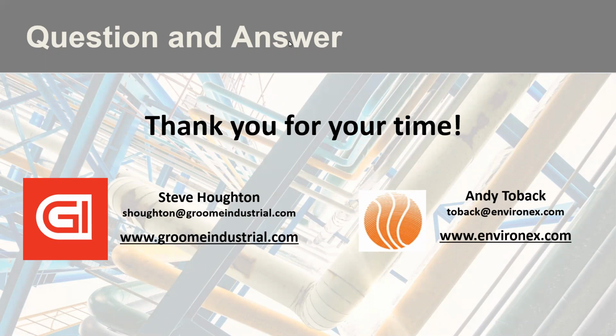Okay, here's one on timing. How long do you expect the tuning to take on an average 7FA? Well, I like 2 days. Recently, I was in a scenario where the plant was really hoping that we could get it done in 1 day, and there's just a calamity of issues that come up during tuning that are all easy to overcome, that just exist in this complicated of a procedure.